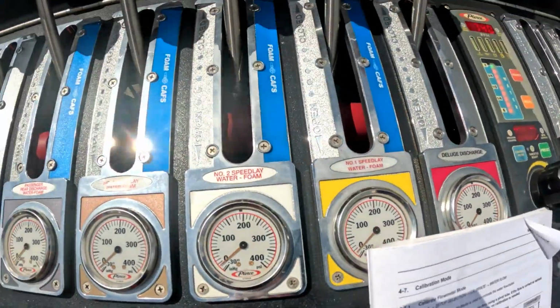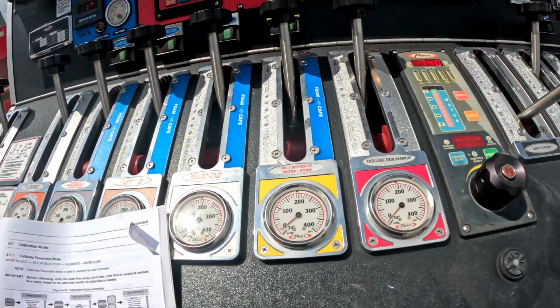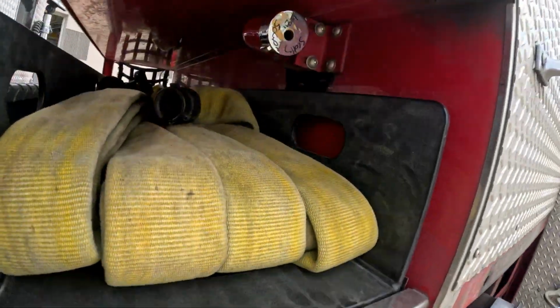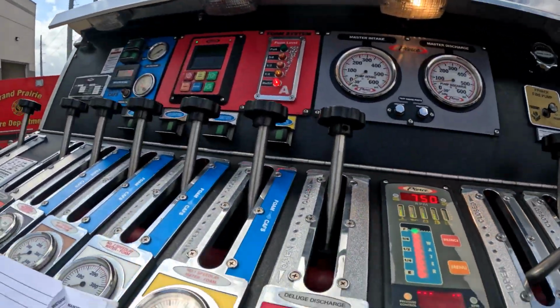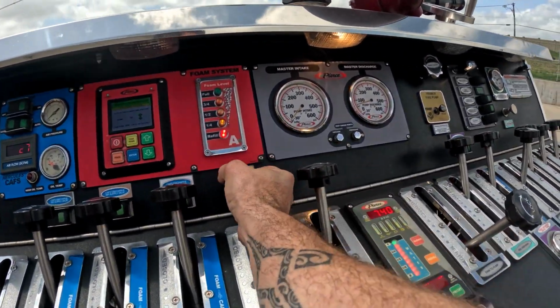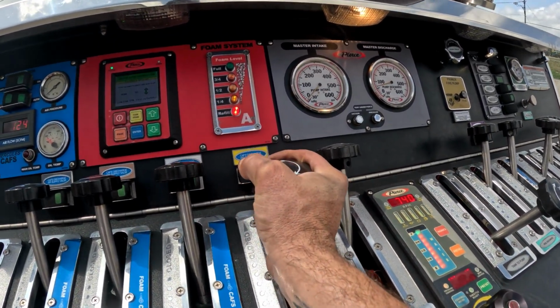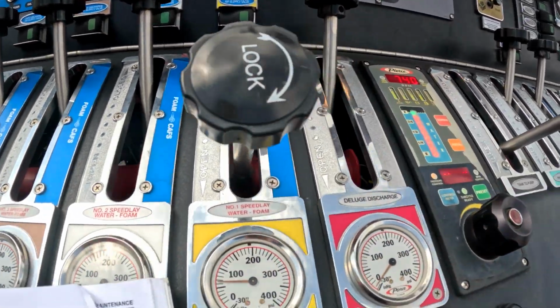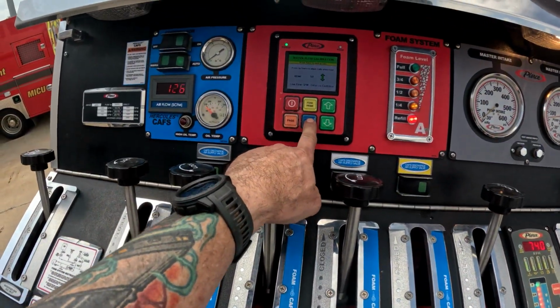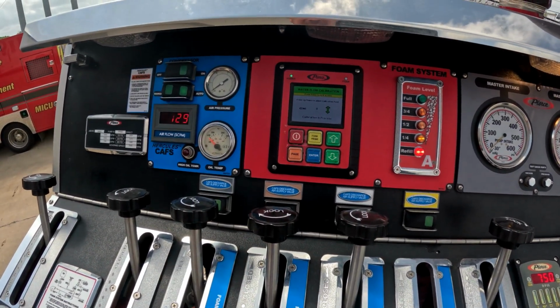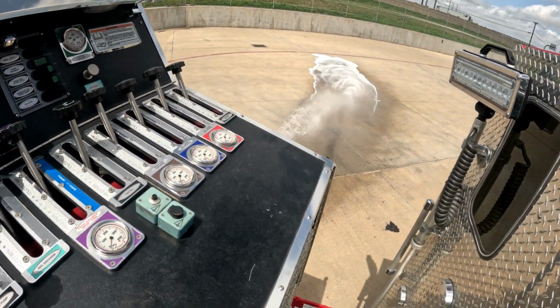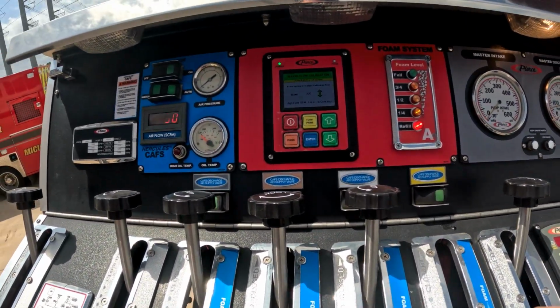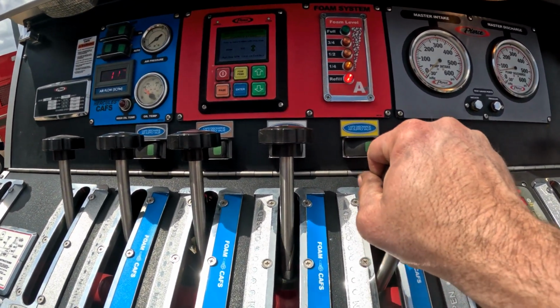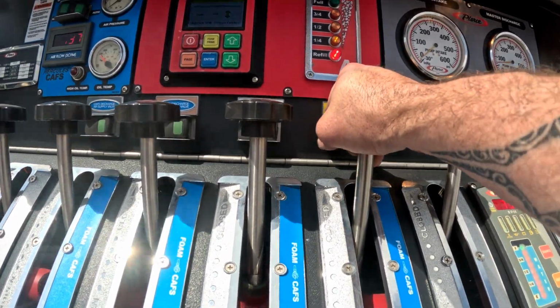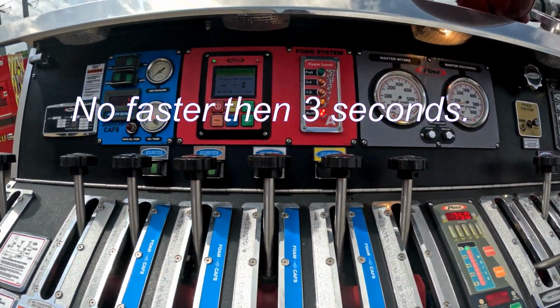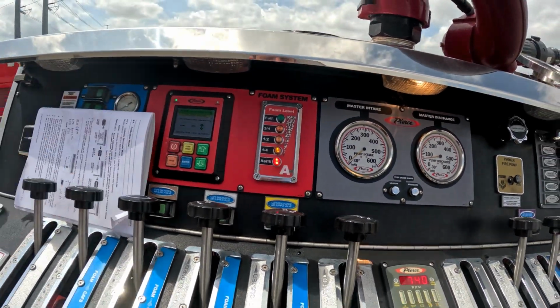All right. So we're gonna verify again that we're on Speedlay #1, yellow. We'll verify it here again, yellow, Speedlay #1. All right. So we're gonna go ahead and start the flow. A little bit above, so we're going to go ahead and enter calibration process. We're still flowing. All right, so it wants me to do the 300. I'm going to go ahead and turn this off. No more than 3 seconds to close the valve. If you slam it in, closing it, you're going to create a water hammer.